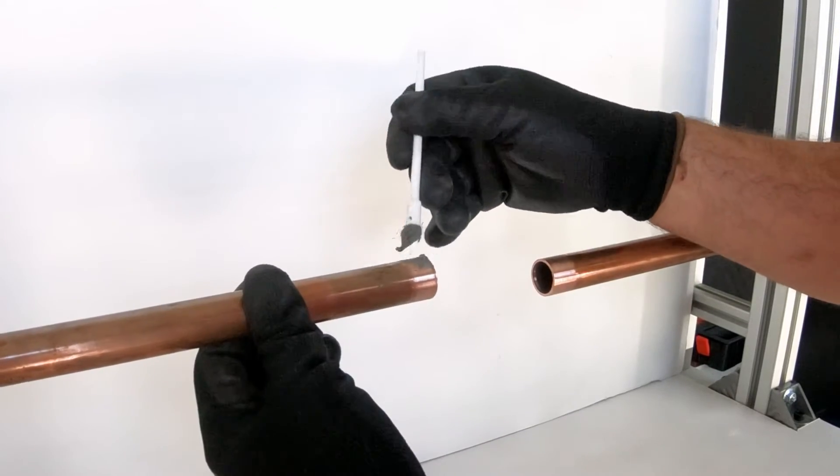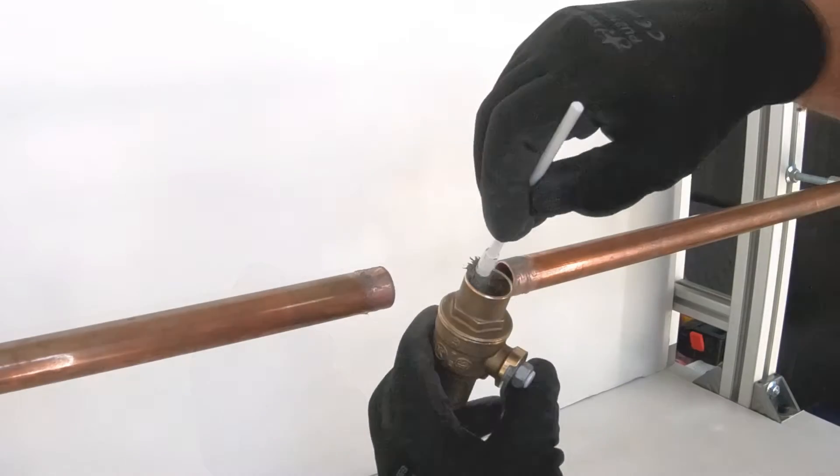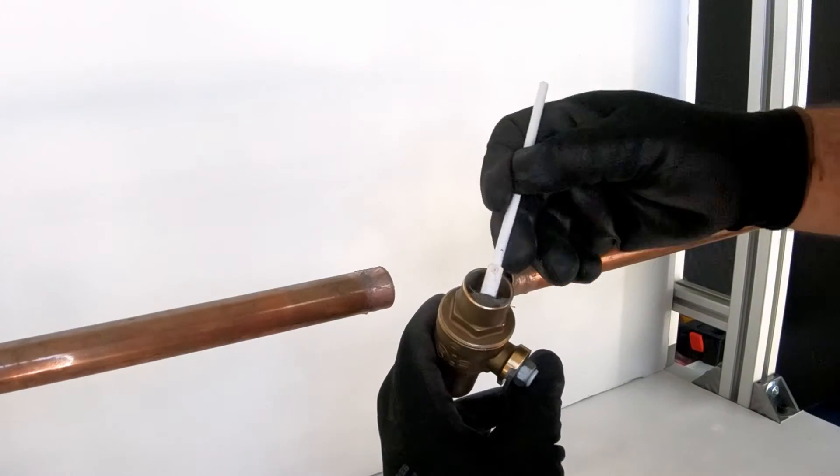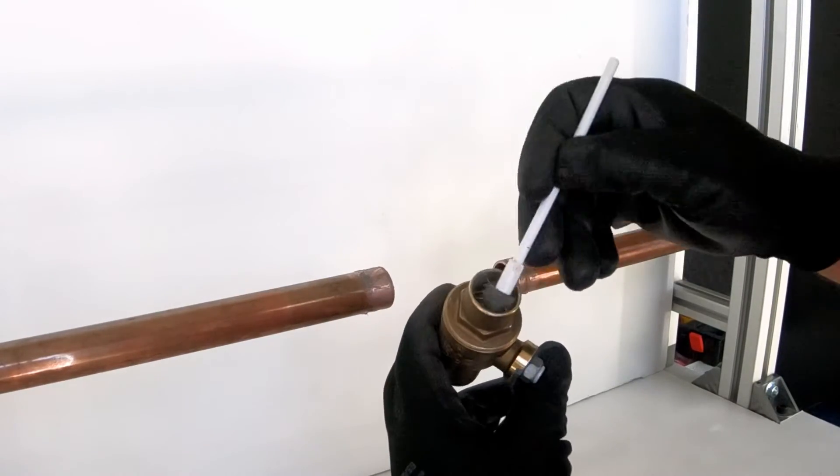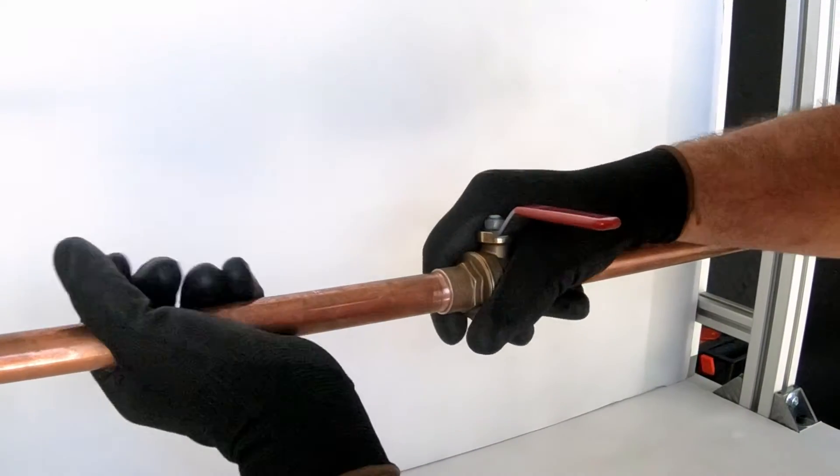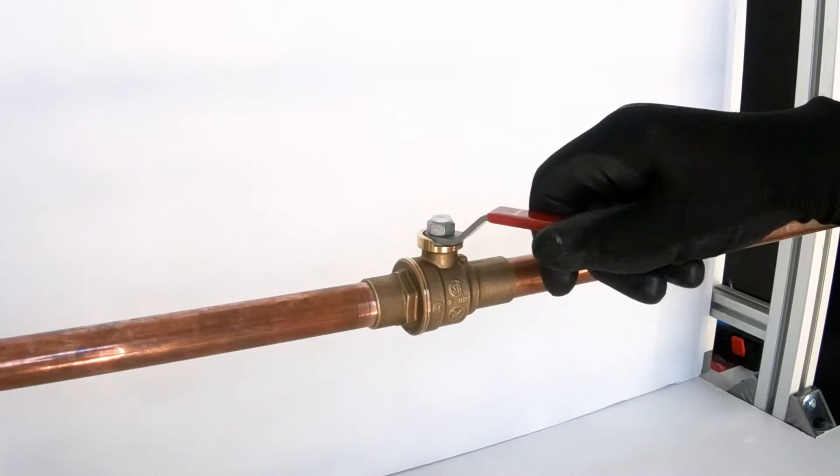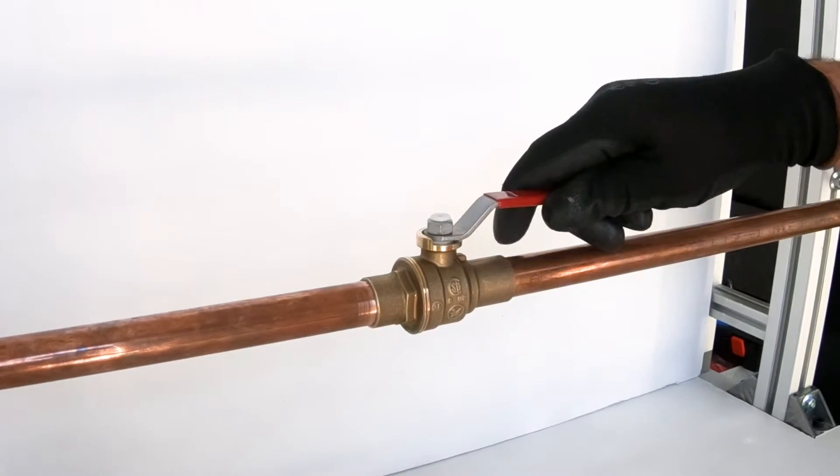First, add flux to both joining surfaces of the tube and valve cups, and insert the pipe into the valve cup. It is important to assure valve is in open position to allow heat to escape.